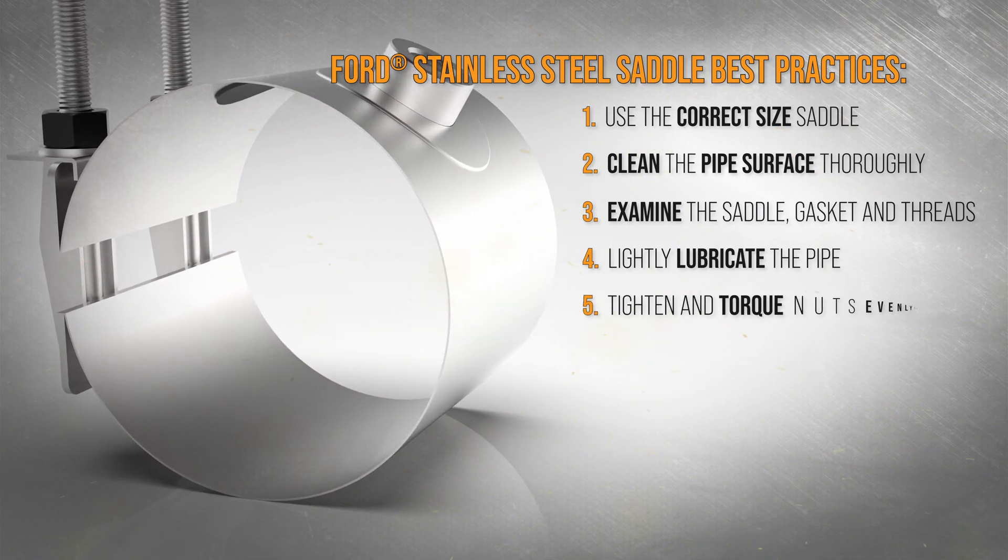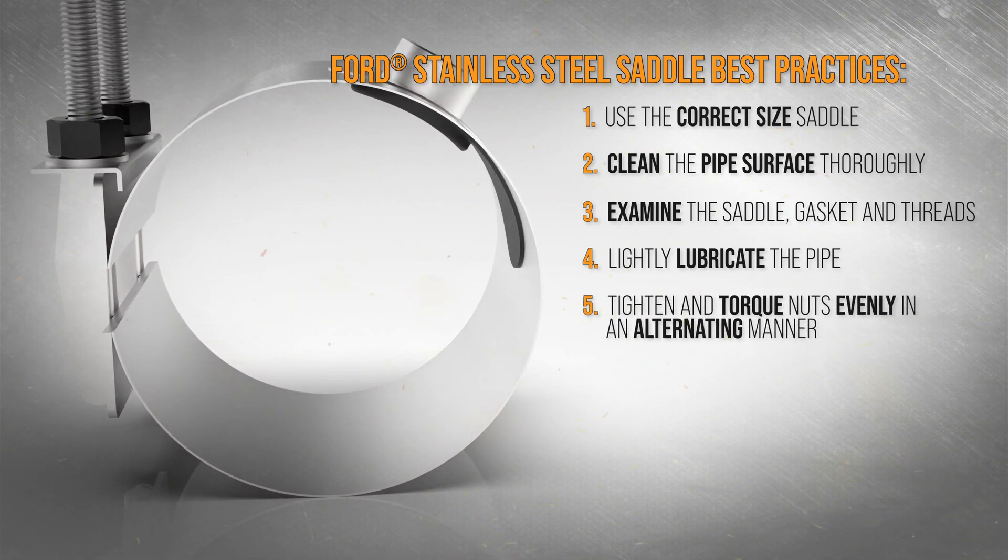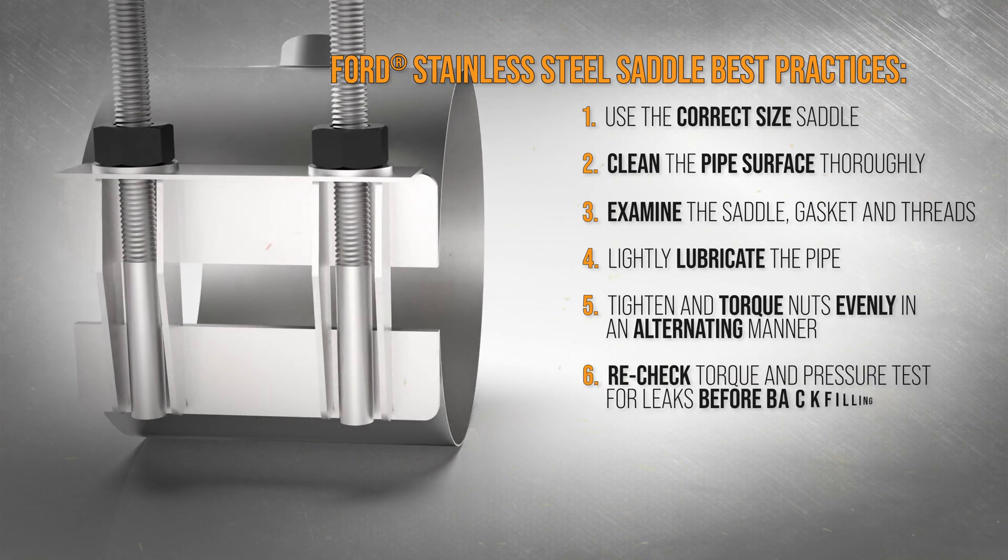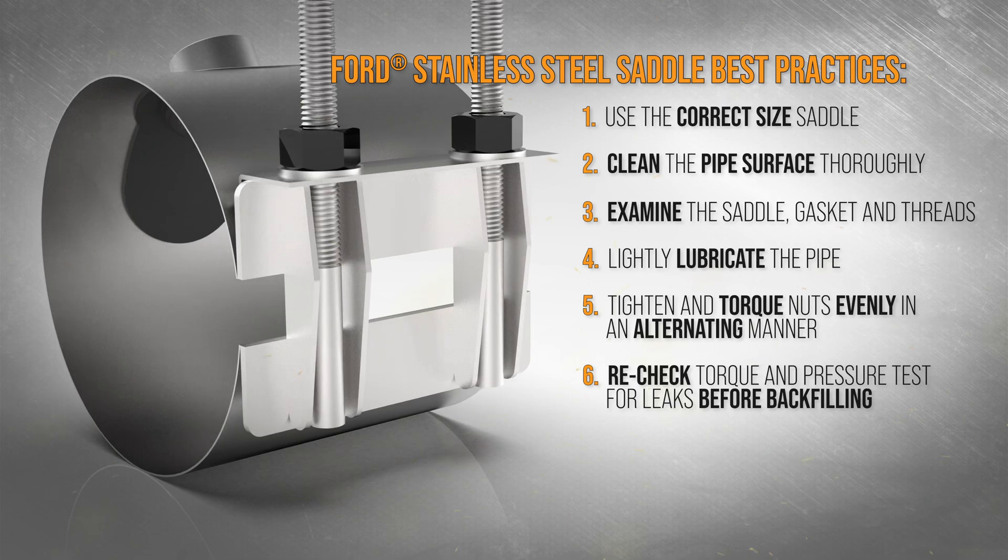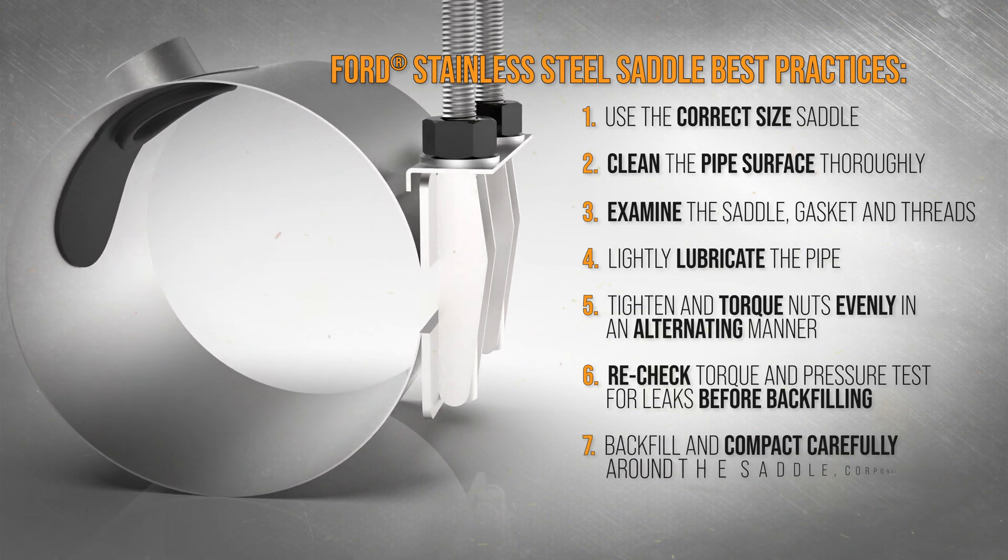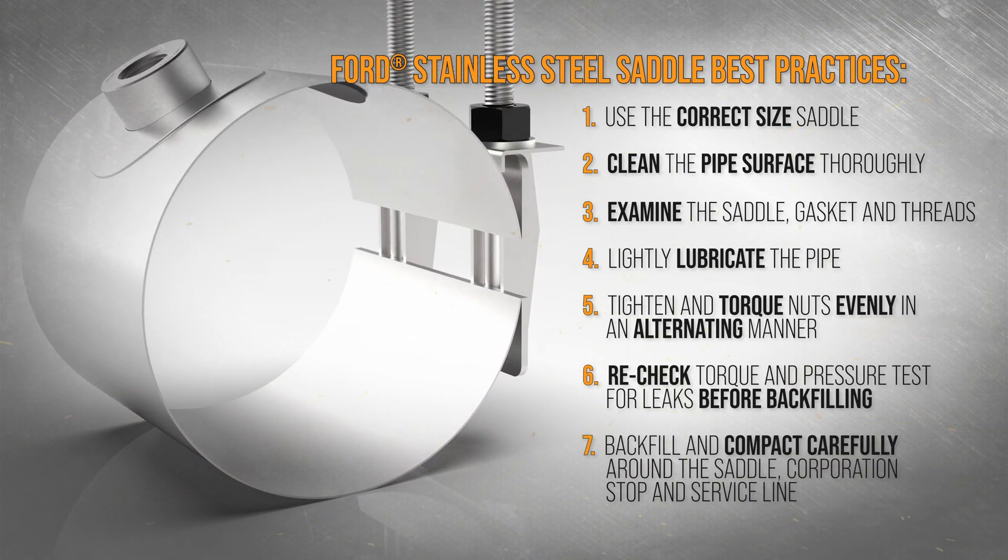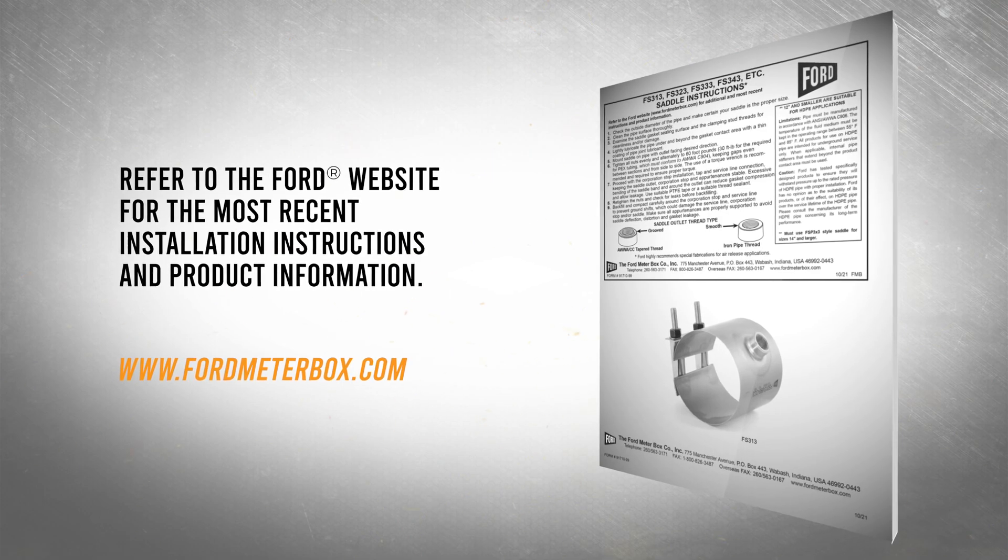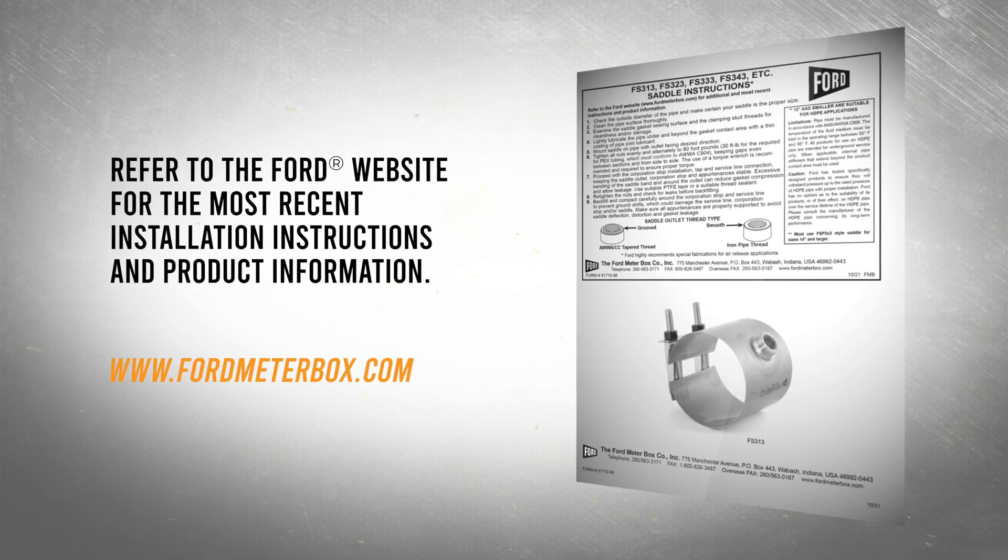Use a torque wrench to tighten all nuts evenly in an alternating manner. Check the torque after initial installation, after pressure testing and again prior to backfilling. Compact carefully around the saddle, corporation stop and service line to prevent ground shifts. Before any installation, refer to the instructions packaged with your Ford product.